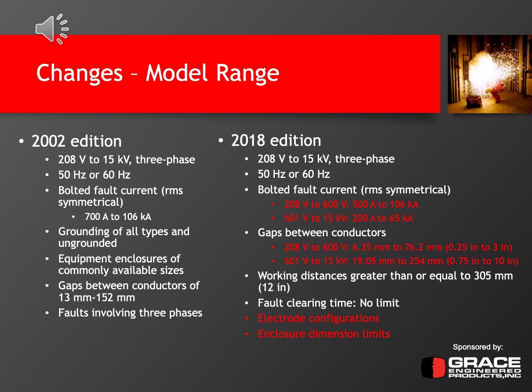In 2018, you still had that same 208 volt to 15 kV 3-phase voltages and the same frequencies, but the RMS symmetrical fault currents have changed. Instead of 700 to 106 K throughout the whole spectrum, from 208 volts to 600 volts it is 500 amps to 106 K, and from 601 volts to 15 kV it goes as little as 200 amps to about 65 K. So that's a substantial difference.